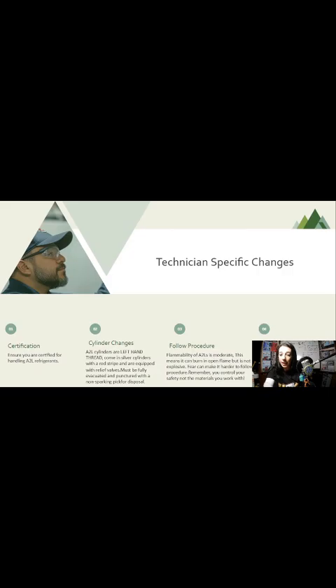Cylinder changes. This is important, you guys. A2L cylinders are left-hand thread. So no righty-tighty, lefty-loosey. Remember that before you ruin the threads. They come in silver cylinders with a red stripe and are equipped with safety relief valves. We have no more pressure plate that blows the whole charge. We now have pressure relief valves. They must be fully evacuated and punctured with a spike for disposal.